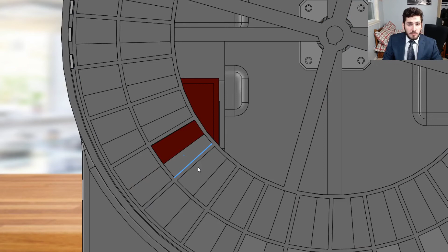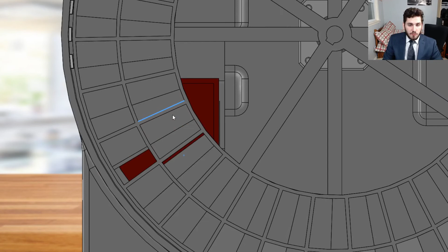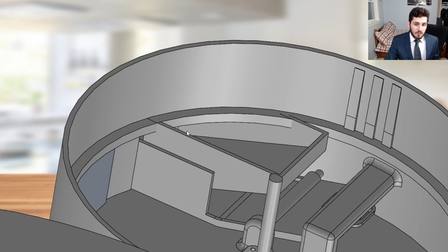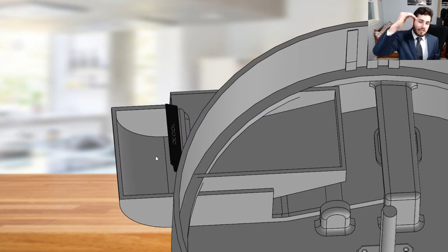As you can see here, as it rotates, only one compartment is open at a time. Then the second compartment opens, and so on and so forth. After the medication falls out of the compartment, it comes into the chute here, which has an angle of 20 degrees, which is more than twice the angle needed to ensure that no medication gets stuck on its way down to the scoop. Now the scoop here has a radius to ensure that someone with minimal dexterity is able to reach their hand in and pull out the medication.